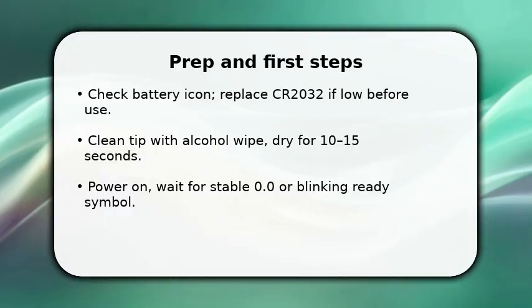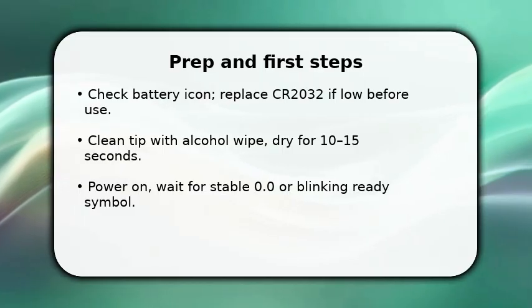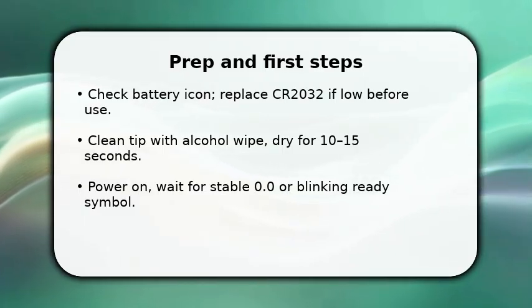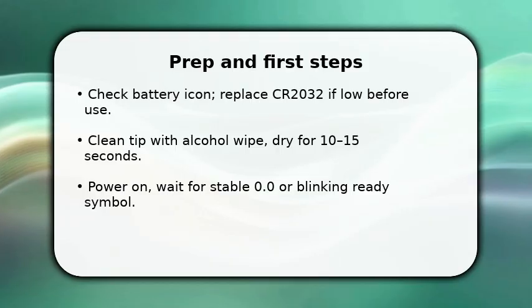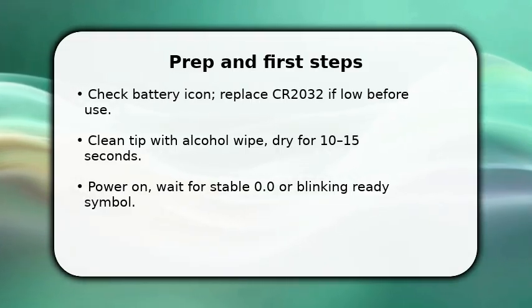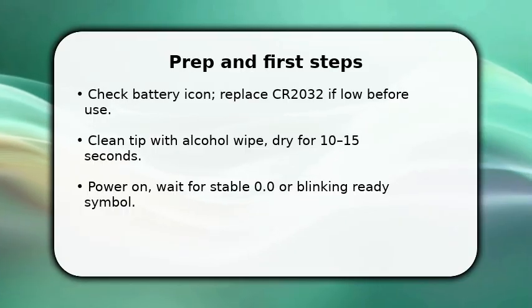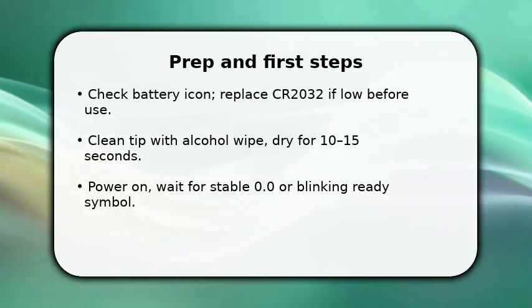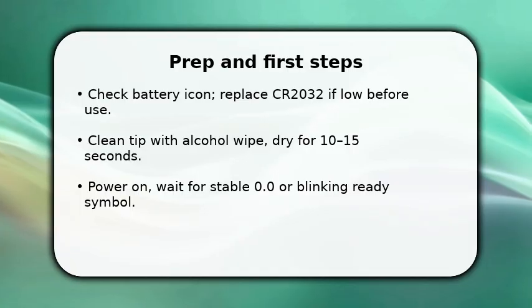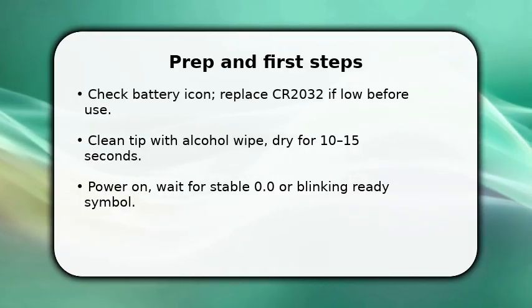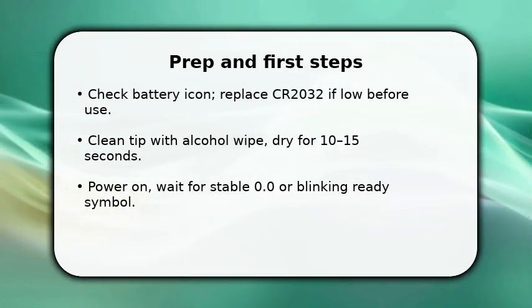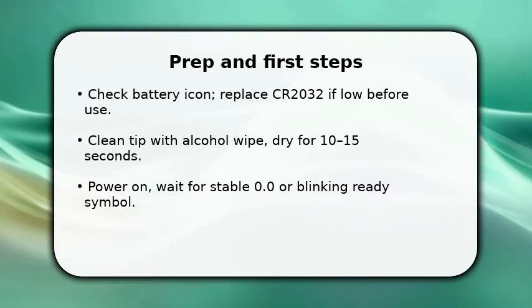You start by confirming basics, battery and cleanliness. Remove the cap, inspect that the CR2032 is seated, swap it if the icon shows low. Once done, wipe the probe with alcohol and let it dry for about 10 to 15 seconds so readings aren't skewed. Turn the thermometer on and watch for the ready symbol or stable 0.0. This ensures the unit is calibrated and ready.